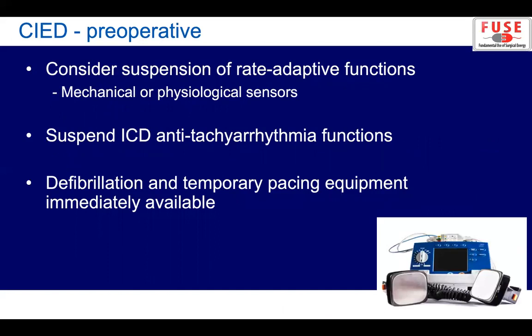Other modes exist. There are certain pacemakers that have rate adaptive functions. You'll see a letter R in the fourth place of the NBG code, so DOOR, for example. These are mechanical or physiologic sensors that will increase the heart rate in response to exercise. That's great if your patient is exercising, but it may not be a desirable increase in heart rate under anesthesia during a hemodynamically unstable situation. So that's something else to keep in mind. Most of the time you do want to suspend the anti-tachyarrhythmia functions of ICDs, otherwise you're placing the patient at risk of an unwarranted shock. Anytime you start suspending functions, make sure you have defibrillation and temporary pacing equipment immediately available.